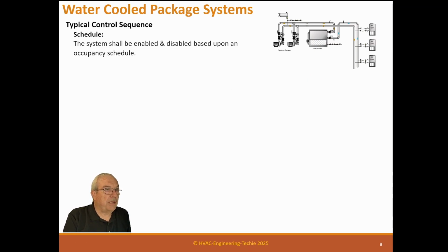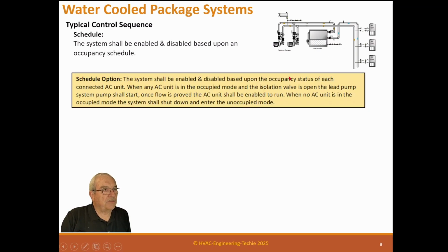Schedule. The system shall be enabled and disabled based upon an occupancy schedule. When do we normally want this building scheduled? Now, you can also do an optional schedule, and that is to have the system turn itself on. You can do that by watching when a heat pump comes in. If all the heat pumps are unoccupied, they're off, so the central plant's off. One becomes occupied for whatever reason, this valve opens, and then it sends a signal to the central plant to start. And so then the differential pressure sensor starts these pumps. So this all starts and can run that unit.